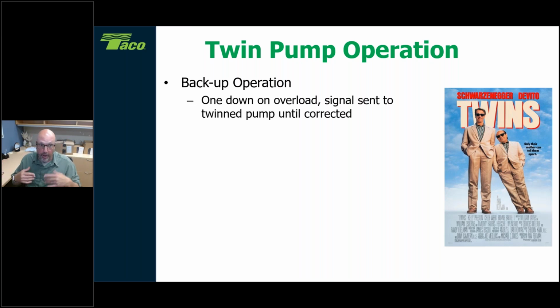So whatever it is, this one's saying overload, but what happens is the second pump kicks in a quick 15 to 20 seconds or so. You could also do cascade operation. So your cascade is going to be, hey, I came up with a project and I need it to flow 300 gallons a minute. And as you guys know, that's pretty darn close to the VR30 maximum flow that it's going to do. But what if I were to have 2 pumps designed to do 150 gallons each? Okay, so now you're cutting down your costs on your circulators and also your power consumption. Instead of having 1 pump to do 300 gallons, I got 2 pumps that can do 150 gallons.